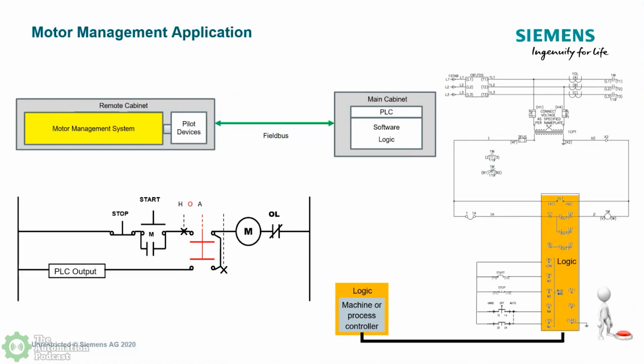Now I want to emphasize local, meaning your hand-off-auto could be right there at the motor control bucket because it has its own 24-volt power supply built in. And then you can power your stop and your start and your hand-off-auto right next to the SIMOCODE. Now, bear in mind, it doesn't have a lot of amperage to try to drive something that's 15 or 20 feet away from it. This is more local, 5 or 6 feet near it, like on a control panel door or an MCC bucket door. But this is introducing it.